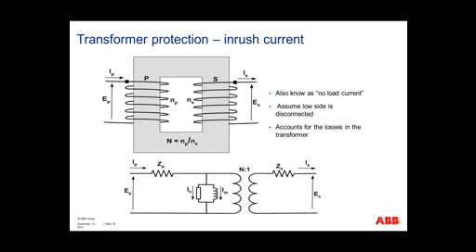Another form of false differential current is inrush current. So we'll go back to our picture of the transformer model and how to represent this inrush current. If we look at our circuit model, I mentioned that IH and IM represent the magnetizing leg, or the current flow on the primary side, which will not produce any current on the low side. So for example, we connect this circuit model, EP, to a source. We open up ES and connect it to no load. We will still have currents circulating through this portion of the transformer. This accounts for the losses of the transformer, the currents you don't see coming out the low side of the transformer.